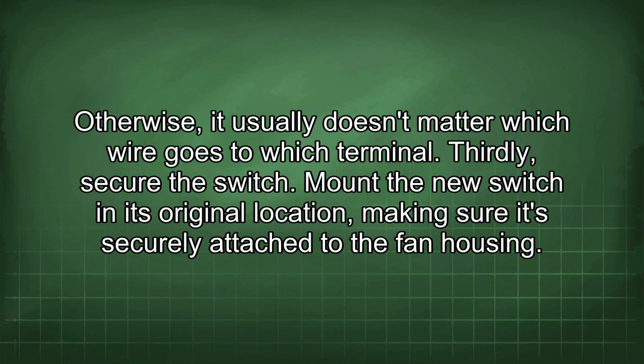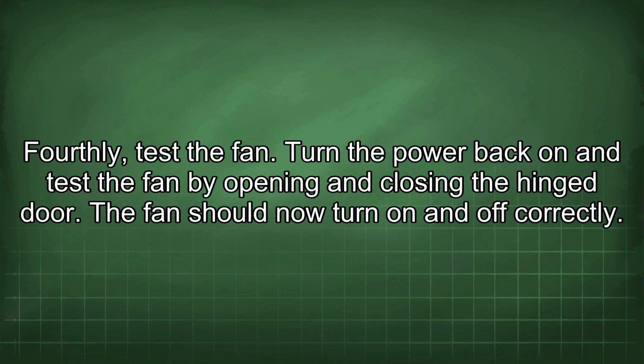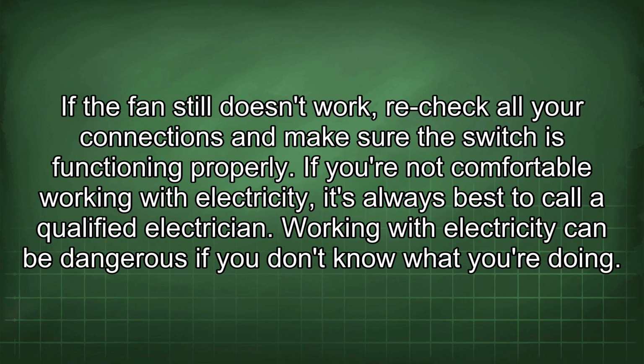Thirdly, secure the switch. Mount the new switch in its original location, making sure it's securely attached to the fan housing. Fourthly, test the fan. Turn the power back on and test the fan by opening and closing the hinge door. The fan should now turn on and off correctly. If the fan still doesn't work, recheck all your connections and make sure the switch is functioning properly.